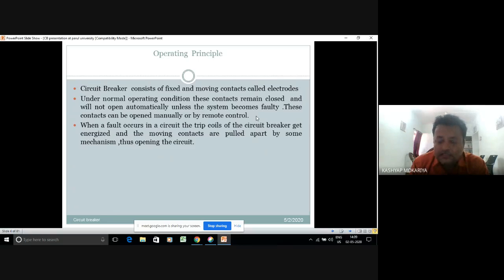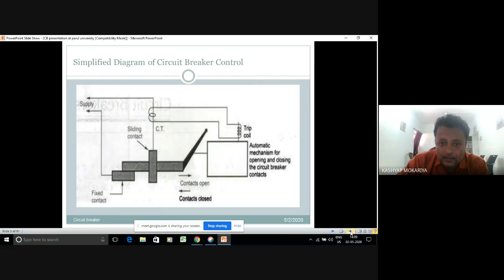When a fault occurs in the circuit, the trip coils of the circuit breaker get energized and the moving contacts are pulled apart by some mechanism, thus opening the circuit. This is a very basic diagram, but if I want to modify it, I will place a contact here. Suppose a DC source is there, a DC source, a control circuit. In industry, generally the control circuit is 110 volt DC, which supplies the trip coil.